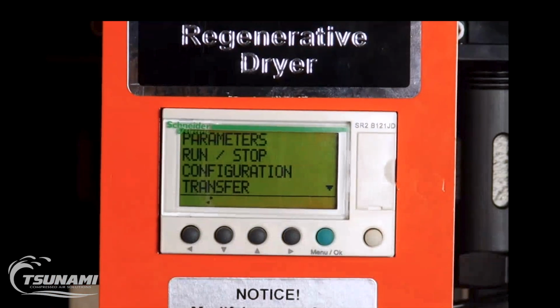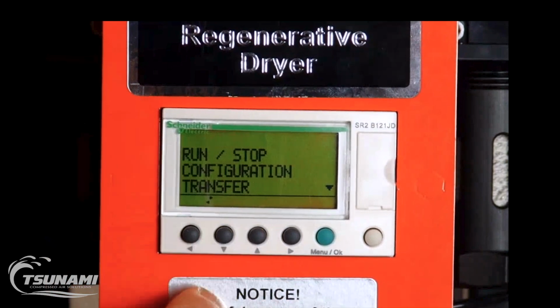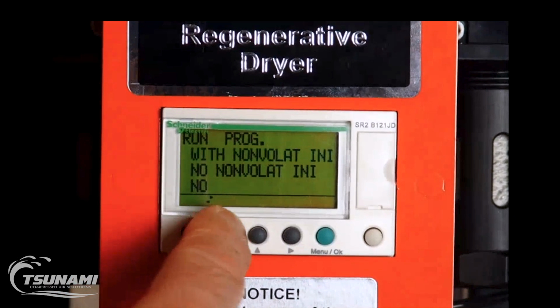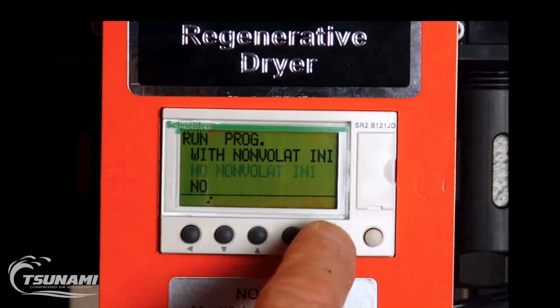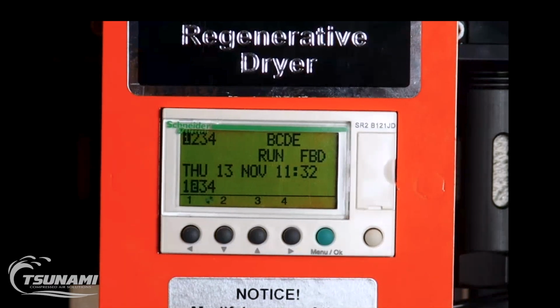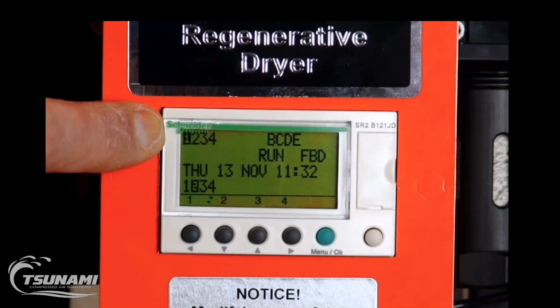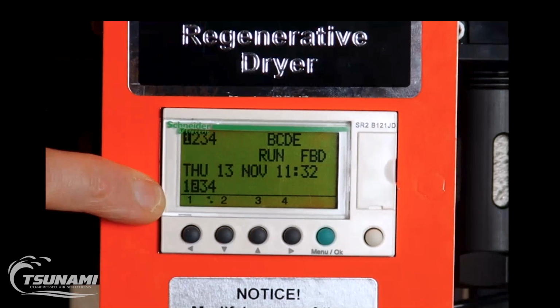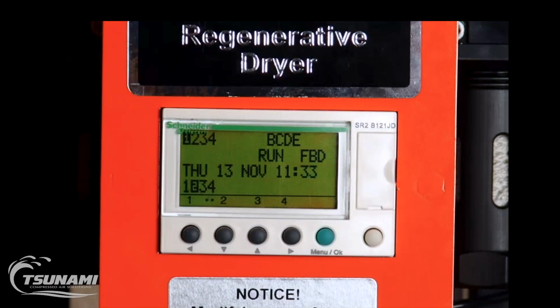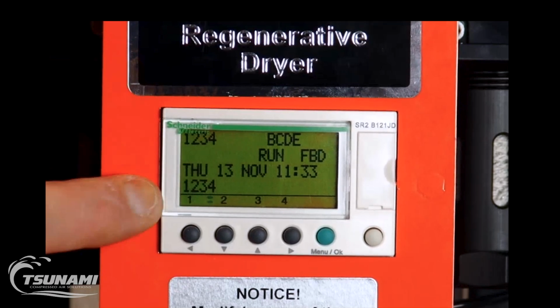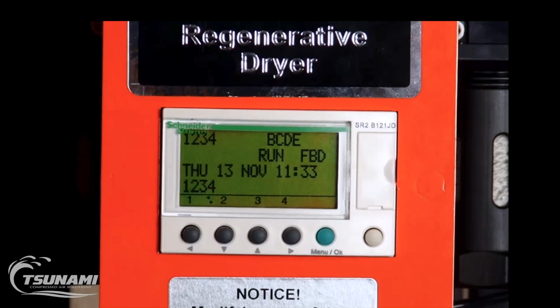And as it's still flashing, we hit the menu button again. We get to run stop. Again, we don't want to reset any of the timers, so no non-volatile. Hit OK. Now, with that digital input or that analog input turning on, the dryer is running. So the compressor's running, it's sending the signal to the PLC. Now that compressor goes into an unload mode, or it shuts off in the case of a piston compressor, and that transducer reads pressure below 80 psi, that signal would go away. Now when that signal goes away, you can see that the PLC program has stopped the dryer from regenerating air.